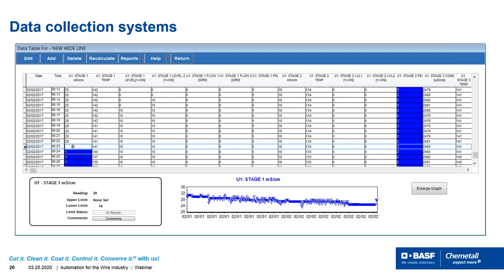Anytime you have any of these alarms, they should be sent out, whether emailed or sent via text message, so somebody can be notified about these things and address them right away when they occur. Pipes break, pumps go down, valves hang up and overflow. Having someone notified, not just by a screen changing from red to yellow, but actually alerted so it can be handled promptly, is really important. A good data collection system, a good SCADA system, will allow that to happen for you.